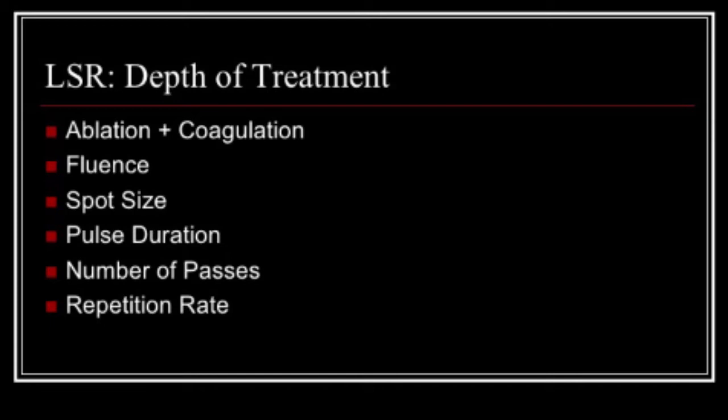I was at a conference in Italy. It was a plastic surgery conference, and one of the plastic surgeons presented a case, and he said this doctor in Pakistan treated this patient with a CO2 pulse laser, and the fluence was very low, the spot size was fine, but the patient ended up with scarring. And I asked him what repetition rate they were using. He said 10. Now 10 is so fast, and if you're not moving your hand fast enough, you're going to stack the pulses, over-treat it, and end up with the scars.